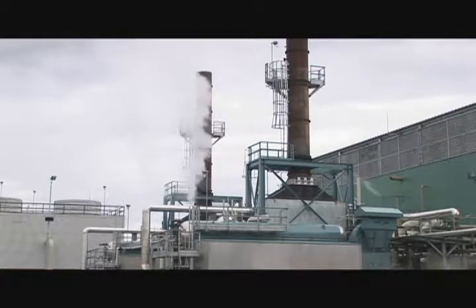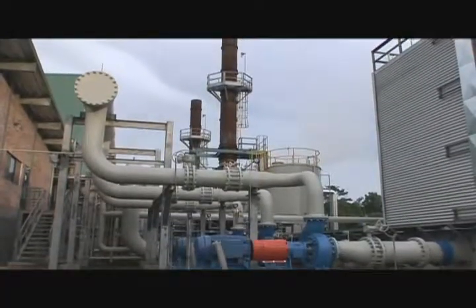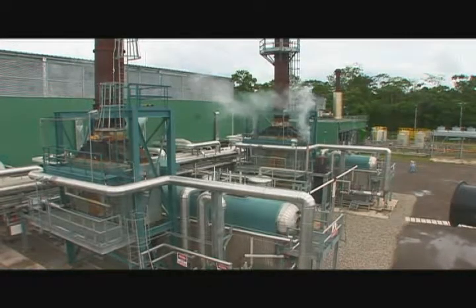It is the first time that this type of generation source has been used in the petroleum fields of Ecuador. The installation consists of a dual system of gas and crude, formed by two boilers and two six-megawatt generator turbines. The boilers have a special burning technology, which has the ability to burn the gas, the crude, or the mix of the two combustibles.